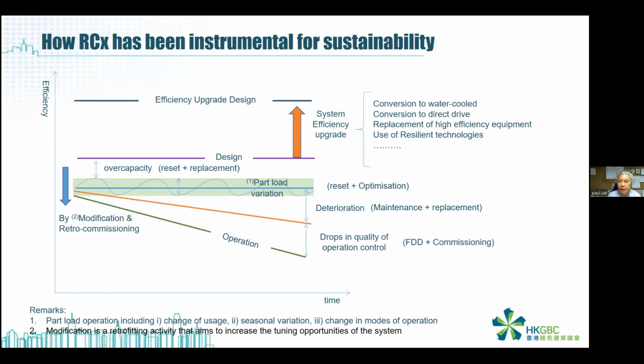And here, this diagram shows how energy efficiency and conservation, or what we call retro-commissioning and retrofitting, can be sustainable. Here you can see that the purple line is the basic design of the buildings. When you move upward, you want to upgrade the efficiency of the design, so you need to take in retrofittings. It will improve the system efficiency. Such retrofittings may include converting air-cooled systems to water-cooled systems, using direct drive, replacing with high efficiency equipment, and also using resilient technology, such as more flexible control technology, something like that.